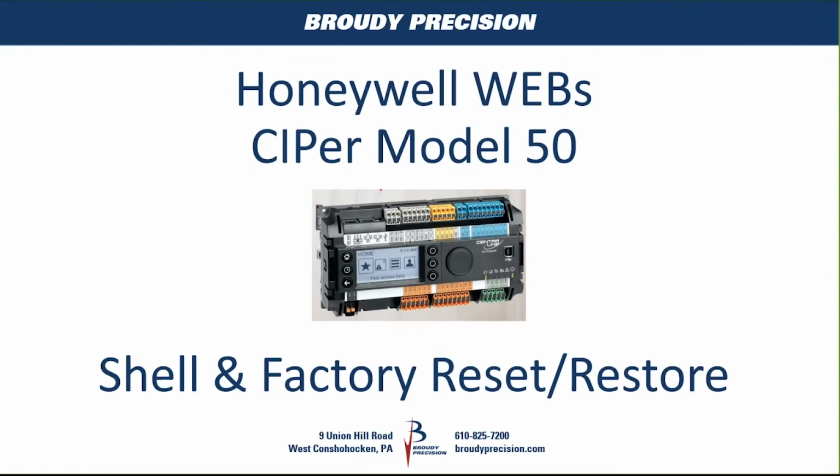One was they had 4.8 running on their CIPer 50, and they had a station that was a 4.7, and they wanted to put it on a site that was 4.7. Doing a clean dist, which is what you would do in a Jace in the past, would take you to the earliest version that it supports. The clean dist for the CIPer 50 keeps you at the version you're at, so it doesn't get you back to the earlier version. So that's one of the main reasons I'm putting this together and have it posted up on our BP Tech Center.